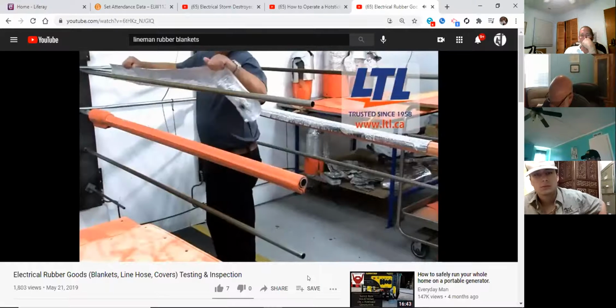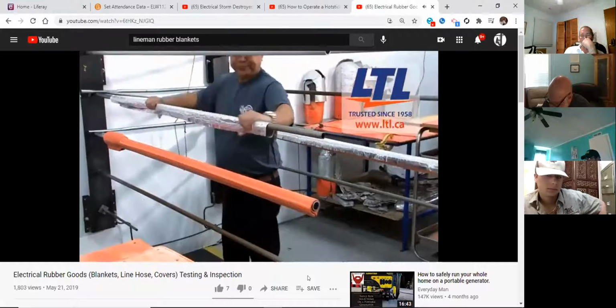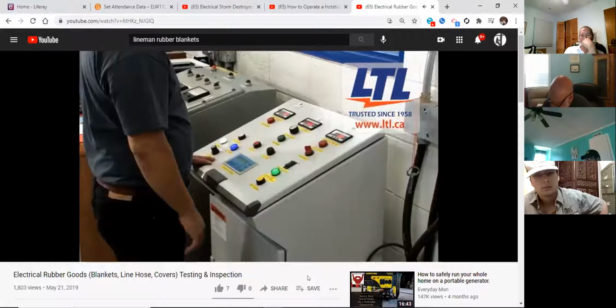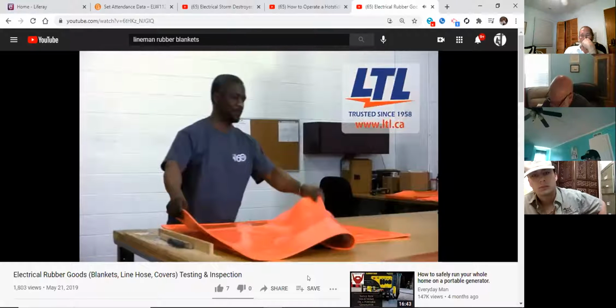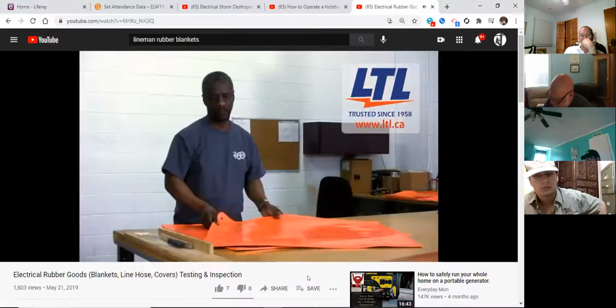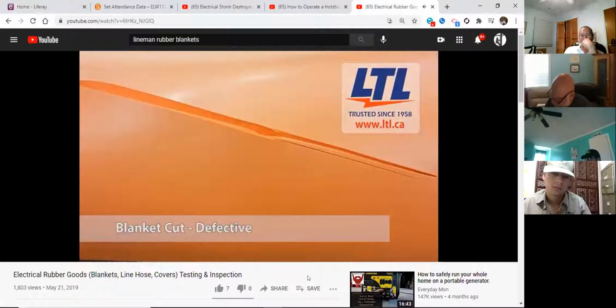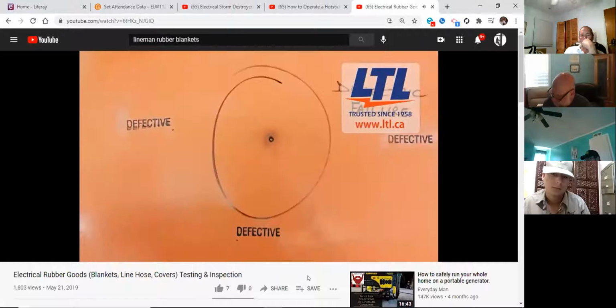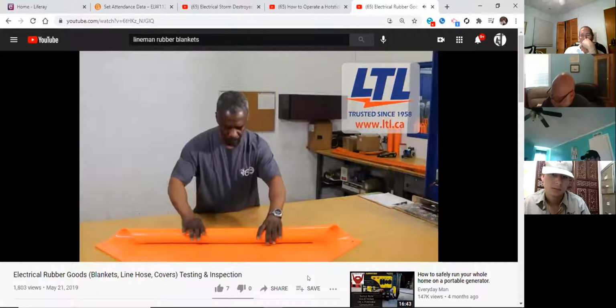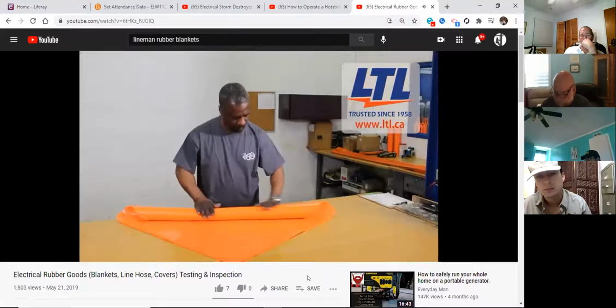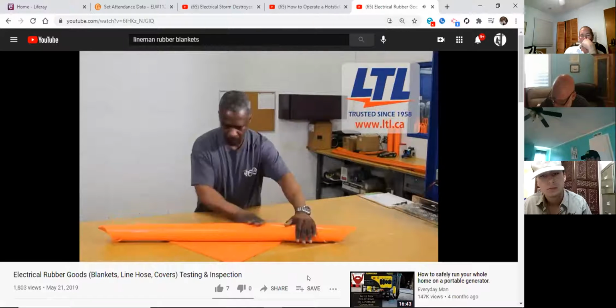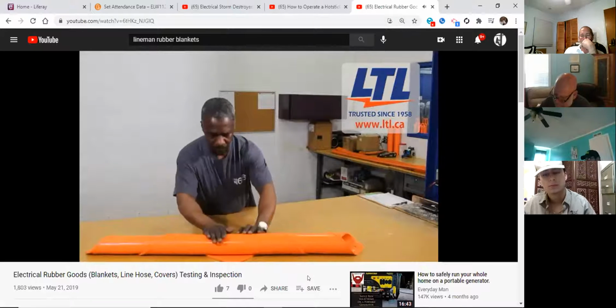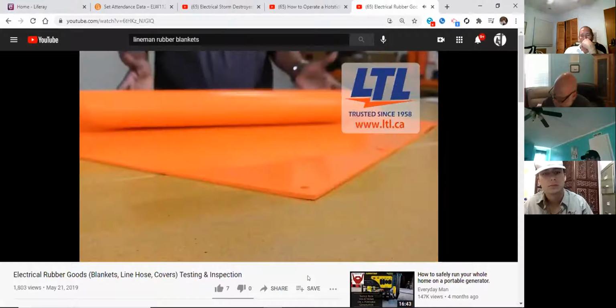When the test is complete, the lab technician moves the PPE to final. In final inspection, blankets are inspected for punctures, cuts, corona cutting, and any obvious condition which would adversely affect the performance as per ASTM F479. The technician rolls the blanket over itself and on both sides to view all surfaces in search of cuts, foreign matter, ozone checking, and dielectrical breakdowns.